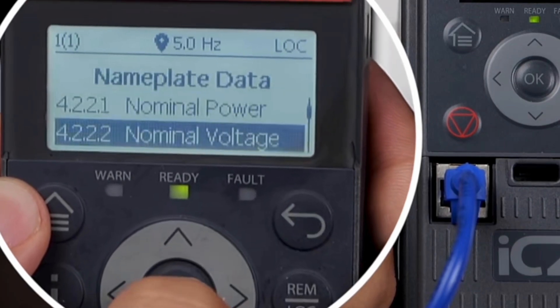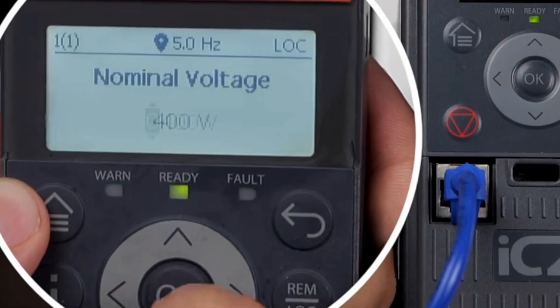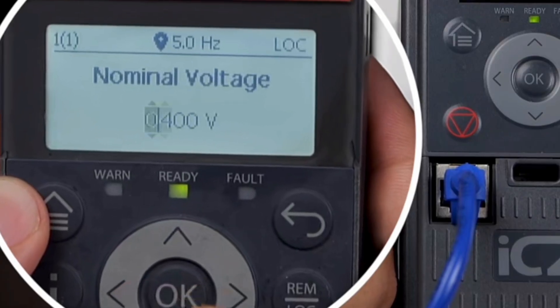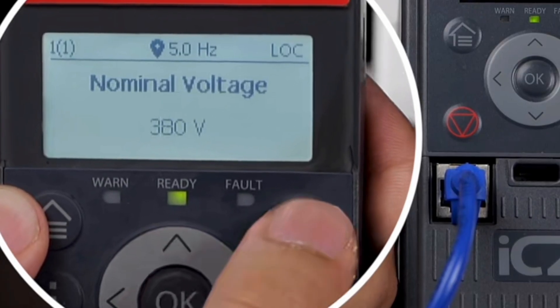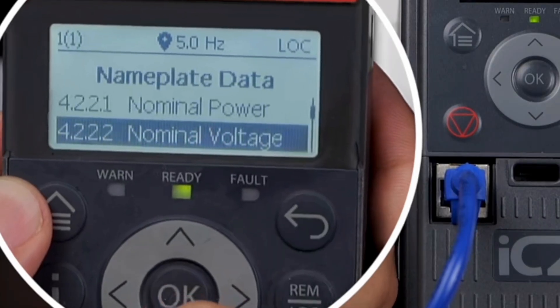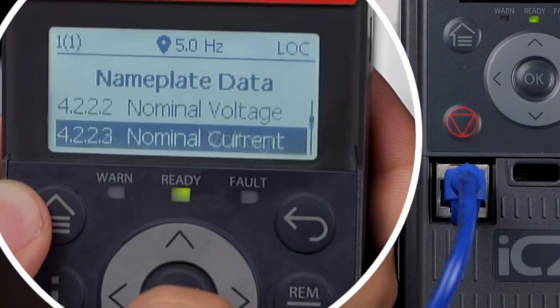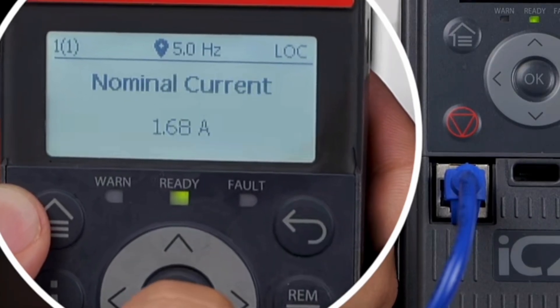Select parameter 4222 and set the motor nominal voltage to 380 volts. Then select parameter 4223 and set the nominal current to 1.58 amps.